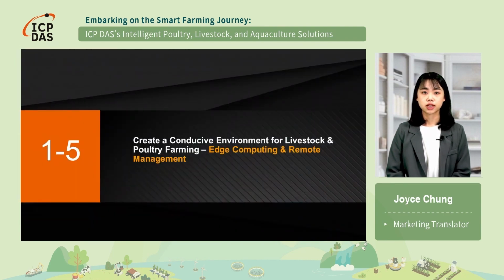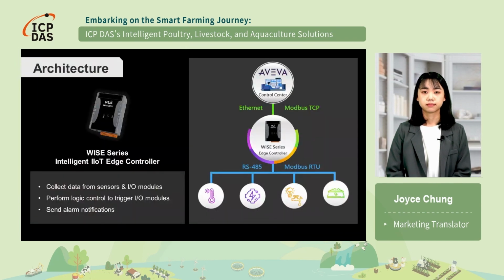Now, let's move on to understand how ICP DAS performs edge computing and remote management in this scenario. In this case, the WISE 5231 Intelligent IIoT Edge Controller is employed to collect every single data of the farm and perform the function of logic control. Once the pre-configured if condition is recognized, the related equipment will be activated using various I/O modules and XV board to keep environmental conditions optimal. When an anomaly is detected, WISE 5231 will send alarm notifications to the right personnel and transmit the data back to the control center via Modbus TCP.